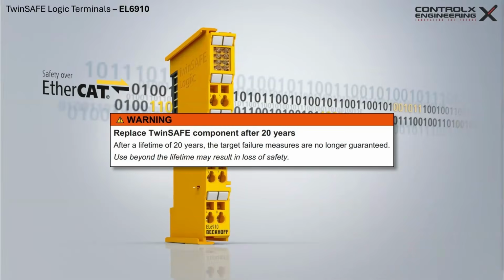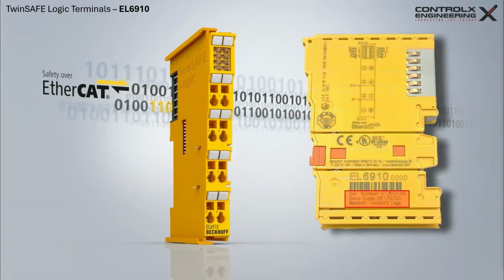TwinSAFE components have a published lifetime of 20 years, during which the target failure measures are guaranteed. The lifetime starts from the date of manufacturing according to the date code. The date code along with the unique serial number are printed on the side of the terminal. And this has the following 8-digit format, where CW is the calendar week of manufacture, YY is the year of manufacture, SW is the software version, and the last 2 digits represent the hardware version.